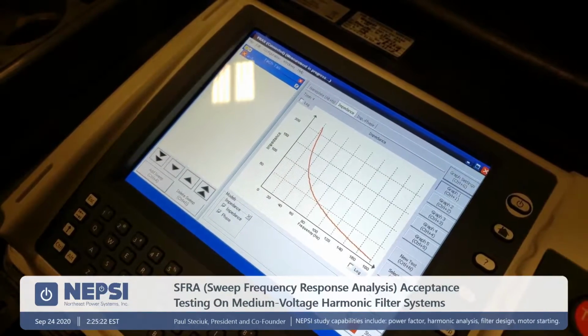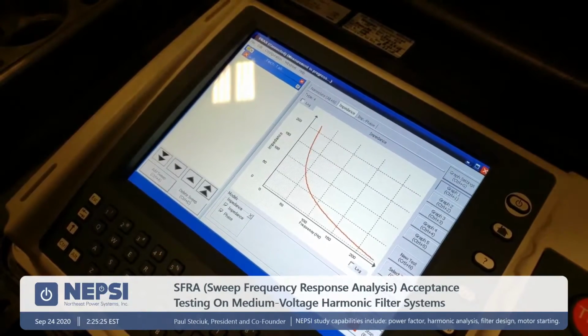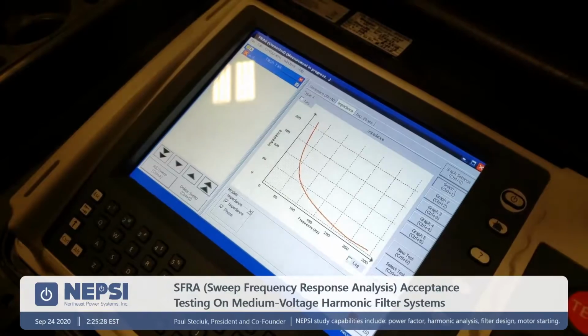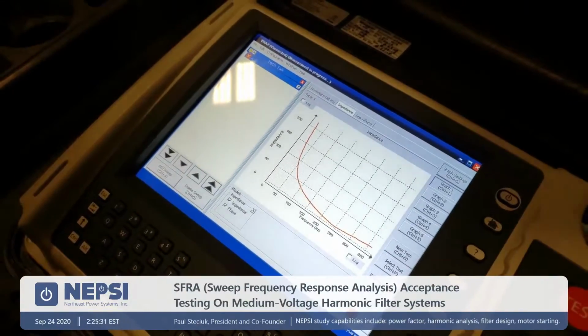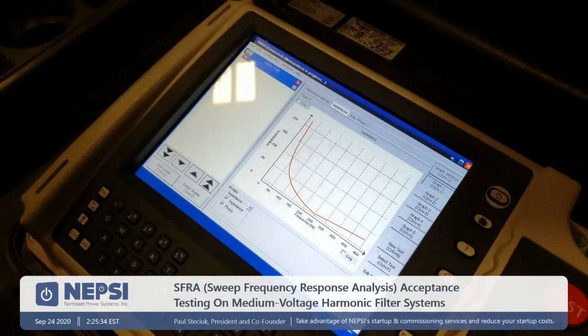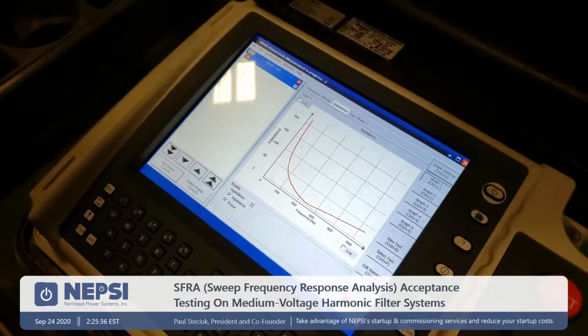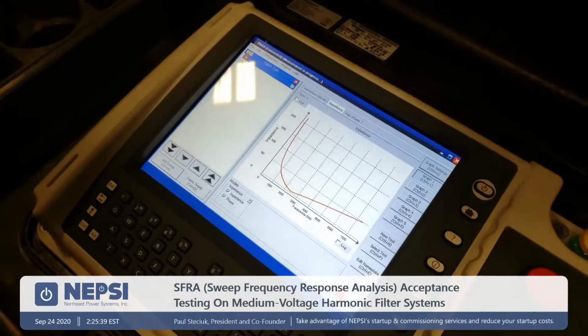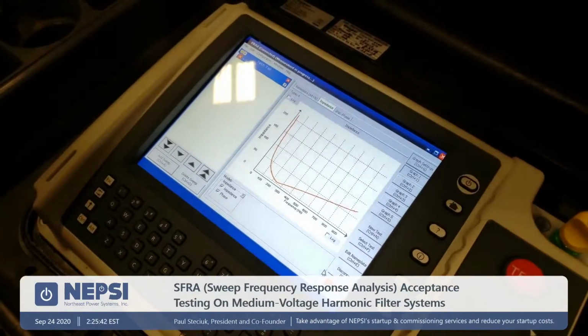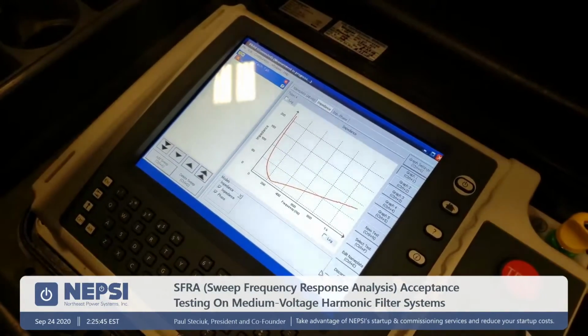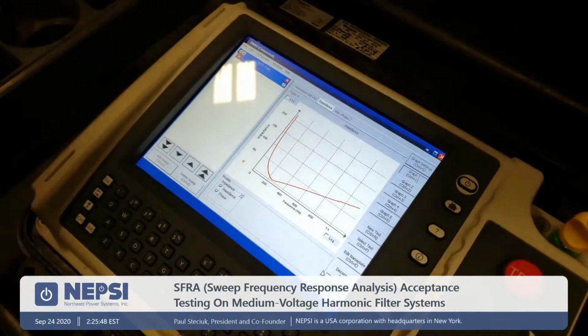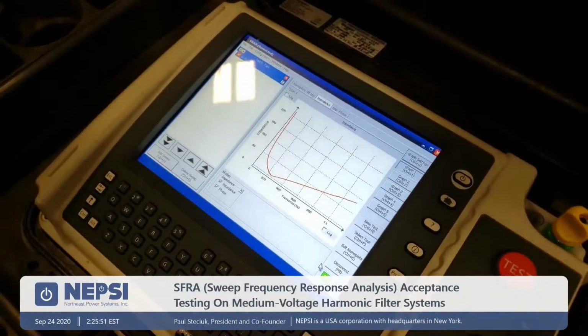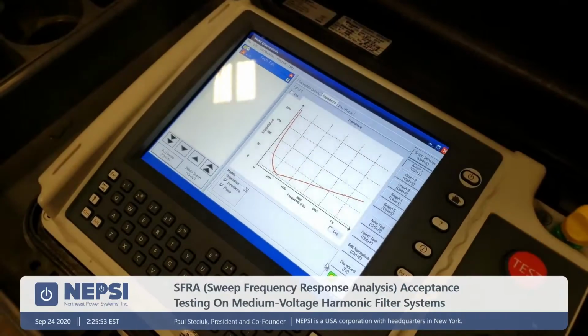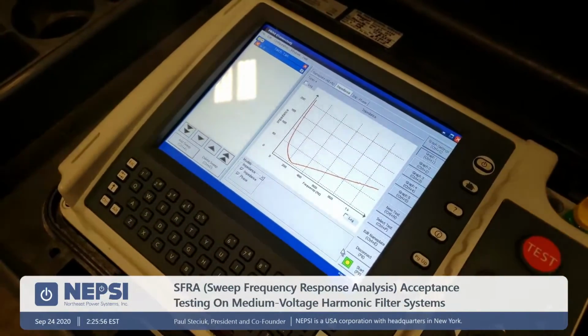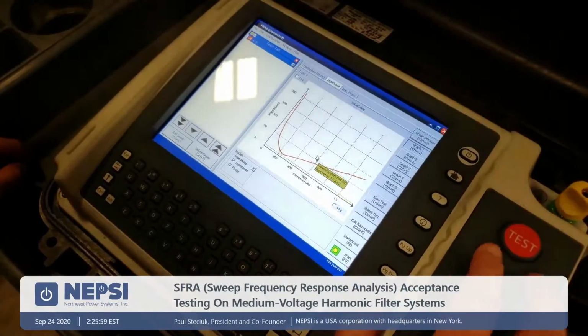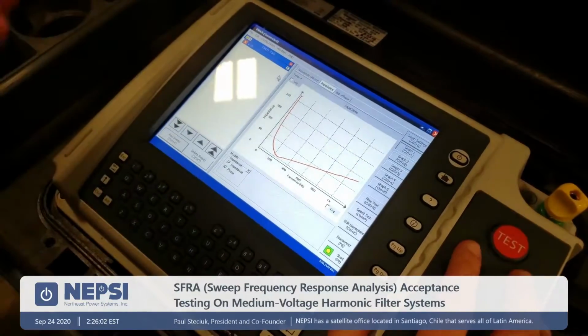No. So if we had a misconnected capacitor, say the neutral is left out, or the capacitor is nameplated wrong, or say the taps on the reactors were incorrectly connected, we would easily start to see it on this impedance scan because we could compare it against the theoretical and it would show itself. Yep. And that's important when you switch from phase A to B and then A to C. We've had tapped reactors where phase C would be tapped wrong, and then the tuning point wouldn't match what it's supposed to be, the theoretical.